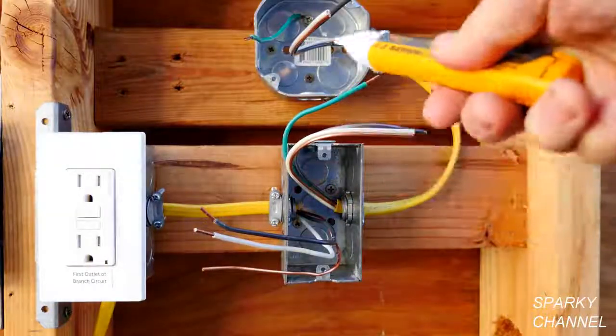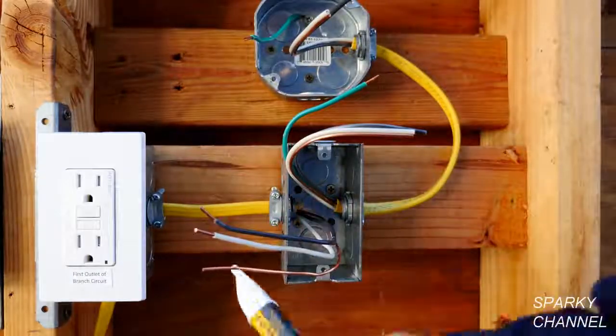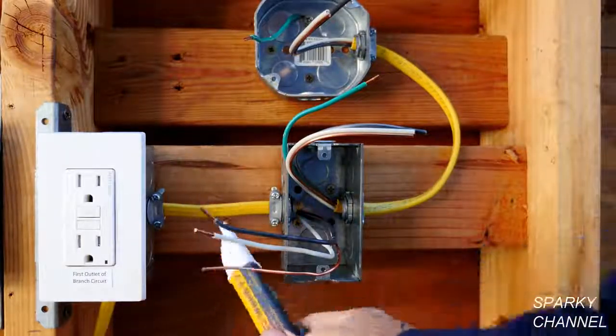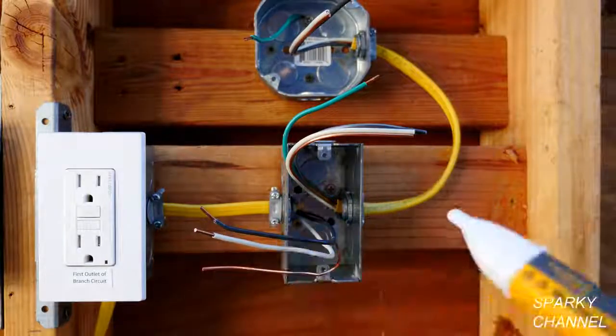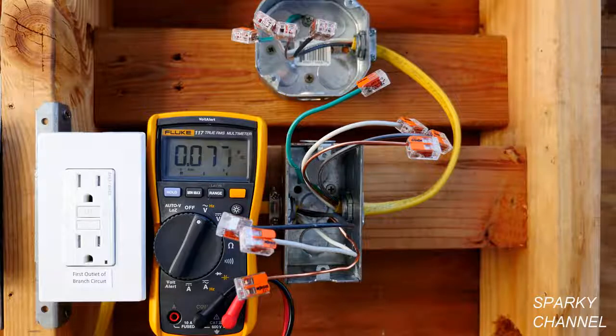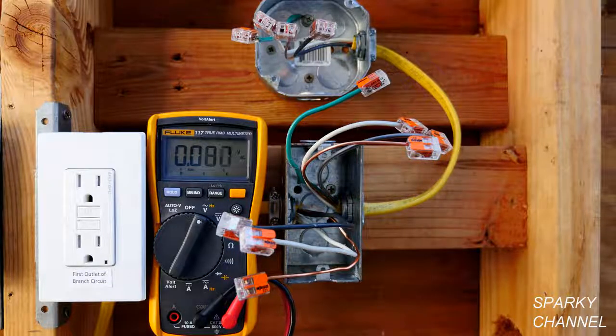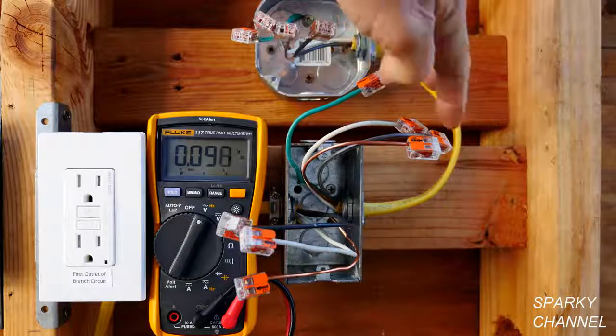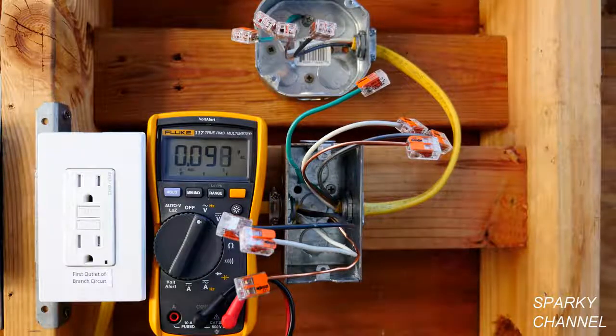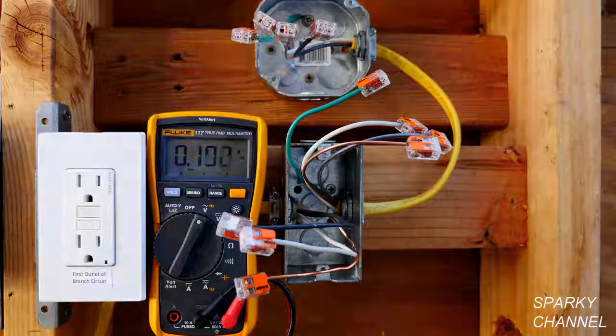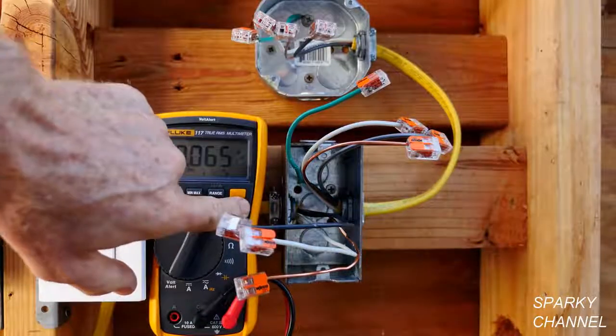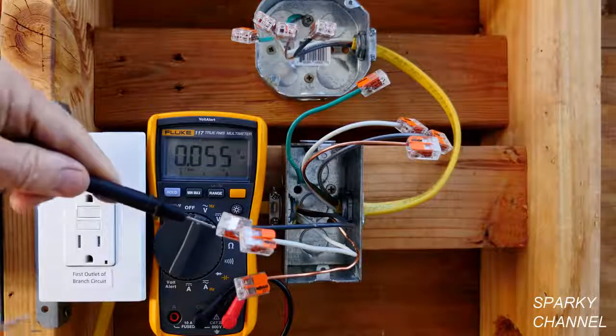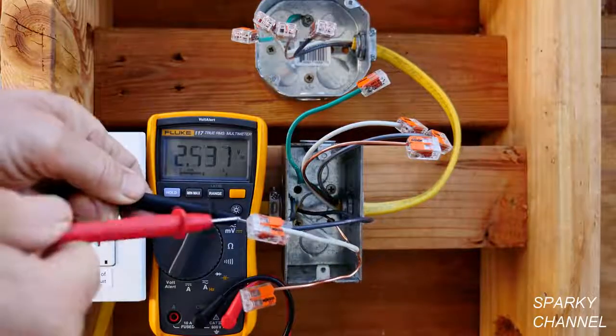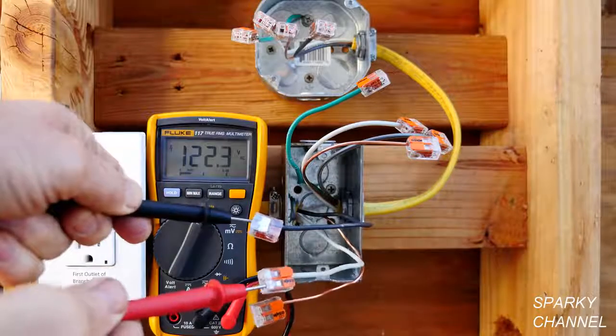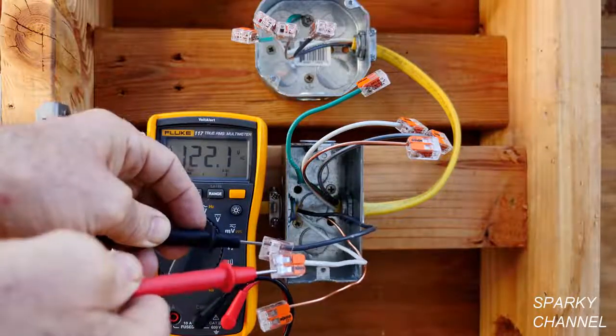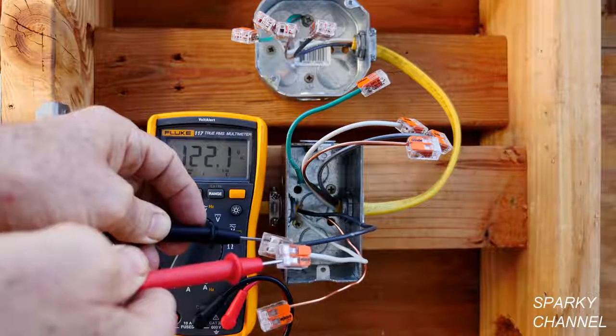Just test all the different wires, and we see that there's no live wires in this circuit because the circuit breaker is indeed off. Before I get started with the installation, I'm going to do a quick test, and I have put Wago lever nuts on all of the wires for safety, and I have turned on the circuit breaker temporarily. And this is my electrician's meter. I'm going to turn the little backlight on, and I'm going to put one lead into the black wire and one to the white wire. And you see we've got 122.1 volts coming into the system.